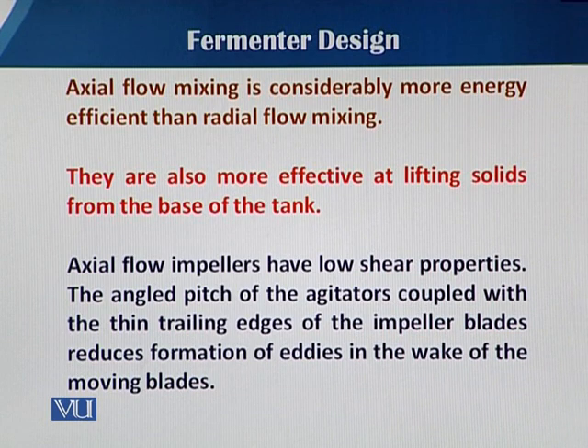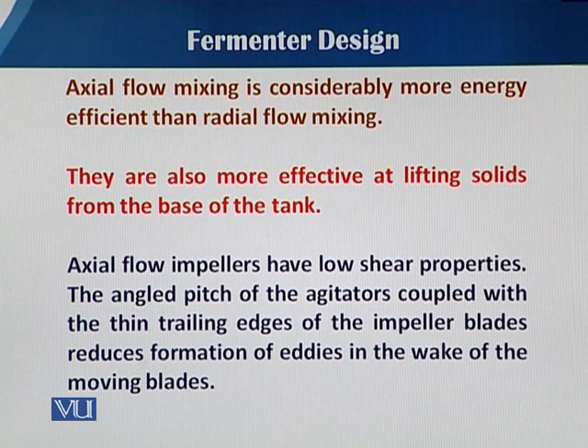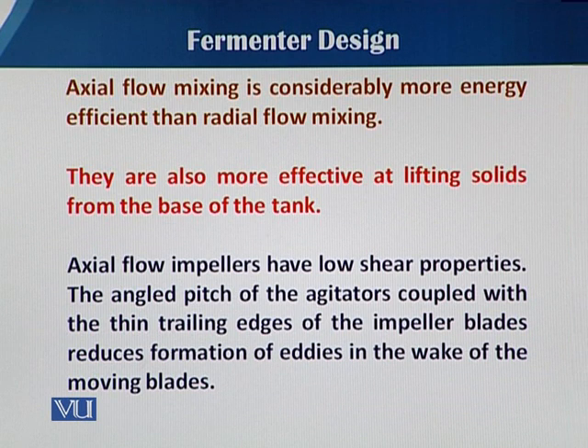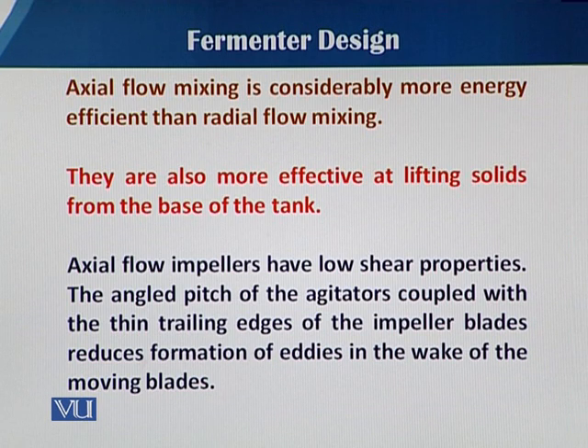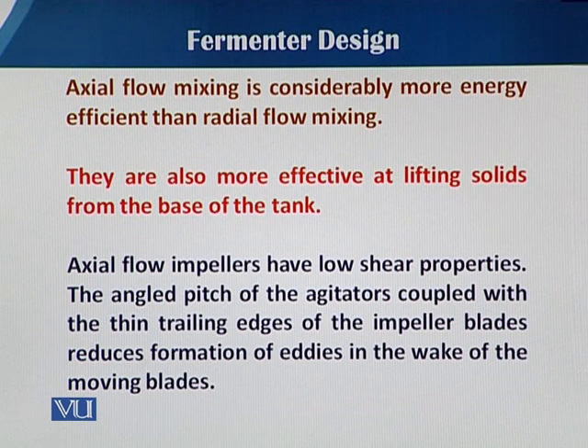Axial flow mixing is considerably more energy efficient than radial flow mixing. Axial flow impellers are mostly designed to decrease energy consumption, and they are used when less shear effect is needed — for example, under sensitive conditions where shear stress should be minimized.